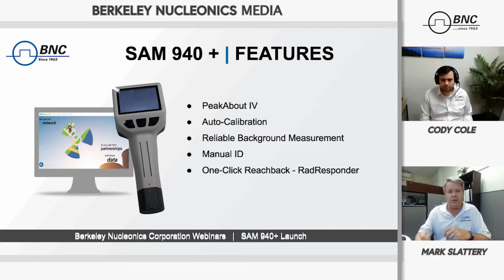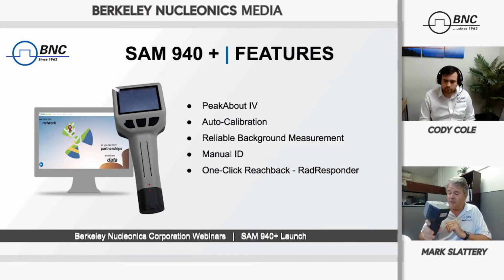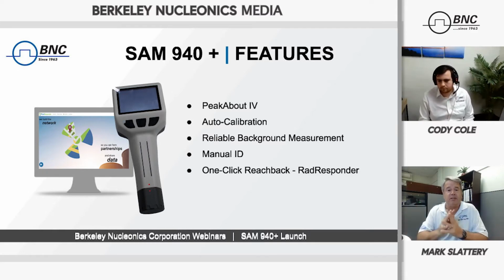And then from that point on, when you're out and about, every second, the device is looking at the radiation levels, comparing it to the background, scanning again, comparing it to the background, and it updates this every second. So that is why it's very important. I may forget to mention it later, or I may mention it too many times, but when you're turning on the SAM, it will perform auto calibration. When auto calibration is complete, you'll likely want to perform a background reference capture. In these instances, you don't want to be in the presence of radiation sources. You don't want any check sources or test sources that you have to be in the region. Please make sure that you are in a fairly benign environment before you turn it on and perform that background. Once it's done, stabilization takes care of that after that point.